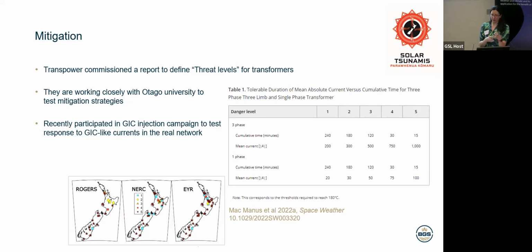It shows you, in this table, the mean current you would need, and for how much time, to get a transformer to 180 degrees. As the size of GIC increases, the time you need to have that GIC for reduces. That means you can do plots, so the plot at the bottom is Daniel running different simulations of different storms using different input assumptions, seeing which transformers in the grid would meet any of these threat levels.